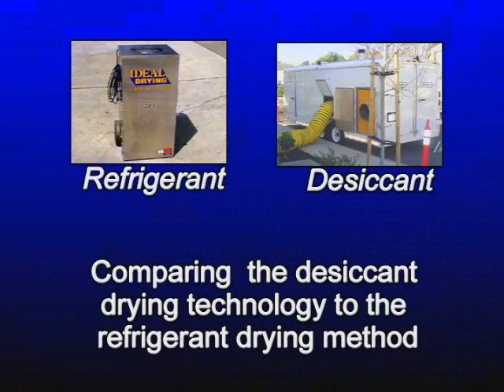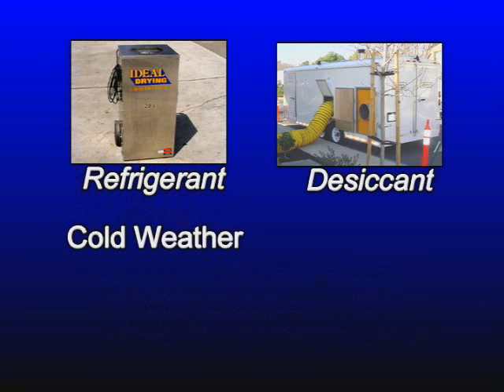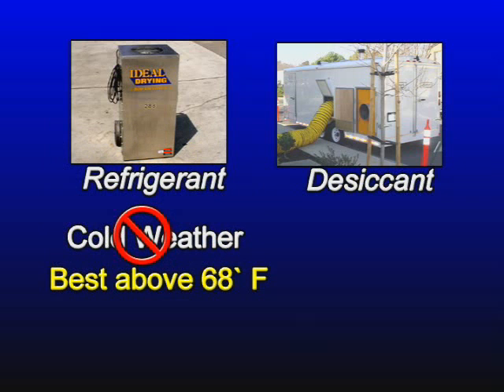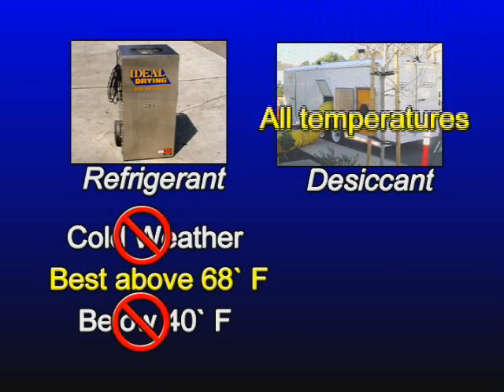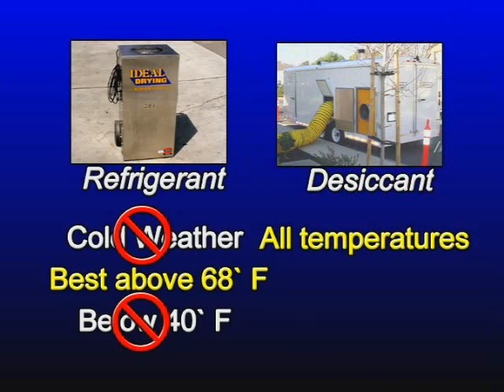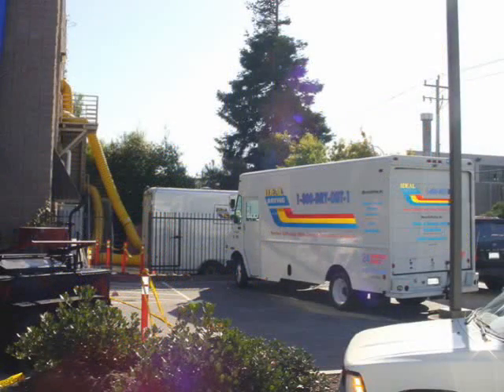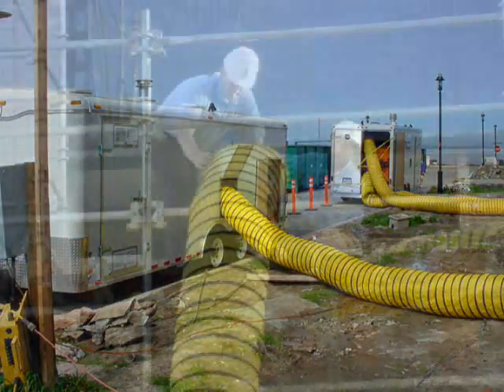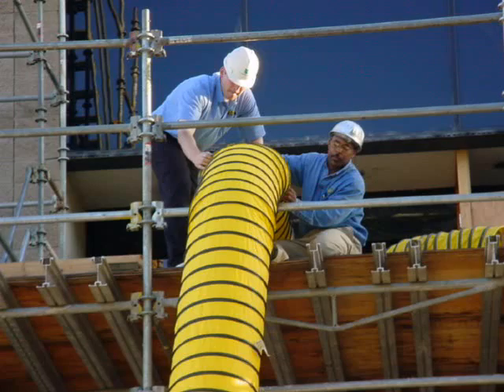Comparing the desiccant drying technology to the refrigerant drying method. Cold weather makes refrigerants work less efficiently. The optimum temperature for a refrigerant is above 68 degrees. Below 68 degrees, the refrigerant will work less and less efficiently until it stops working to any appreciable result below 40 degrees. The desiccant will work at all Northern California temperatures, including temperatures below freezing. The desiccant will also produce a relative humidity approaching zero, which is a humidity rarely found in most deserts.